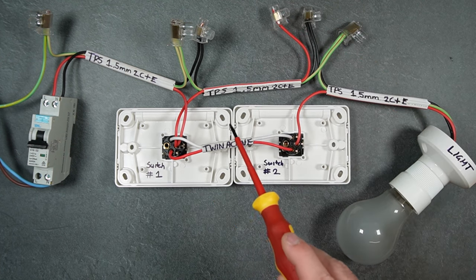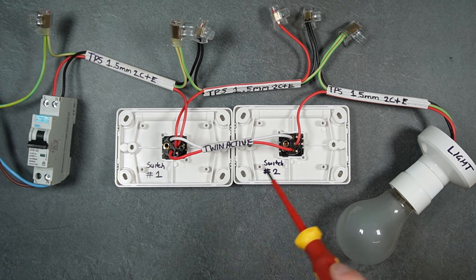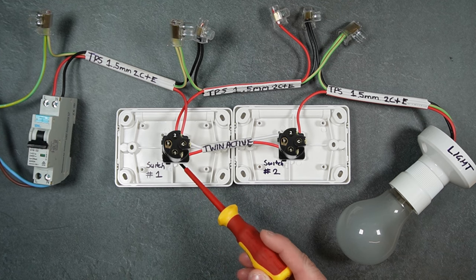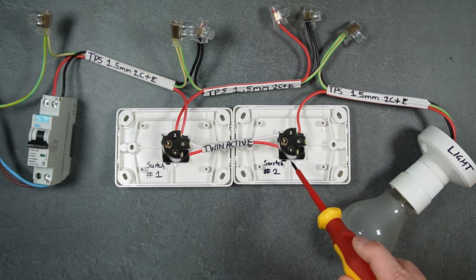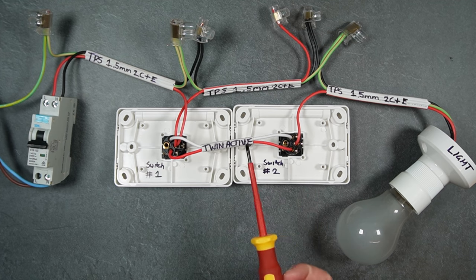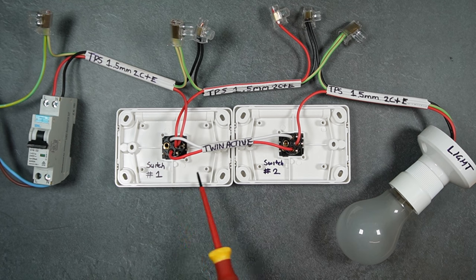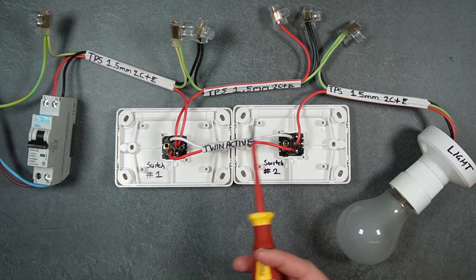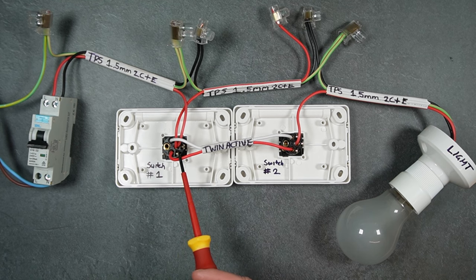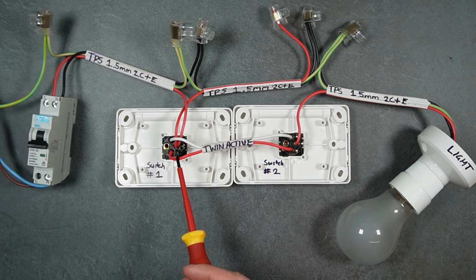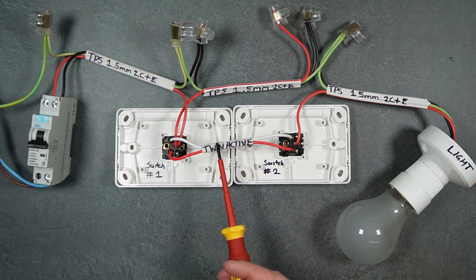I'll explain that in a second. The twin active cable links the two switches using terminals one and two at each switch. It doesn't matter if you use the red or the white to link one and two - I mean by that you can link the number ones with the red or the number ones with the white. It doesn't matter what colors you use as long as they correspond at the other end.